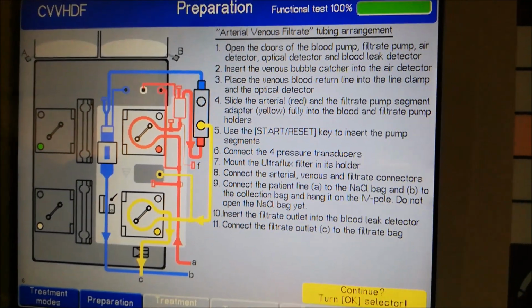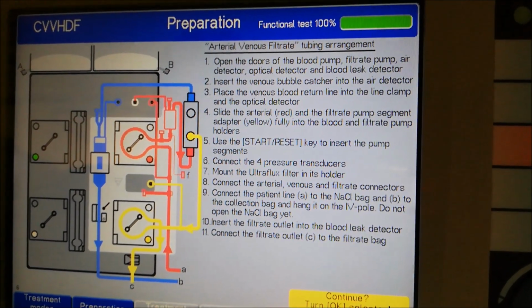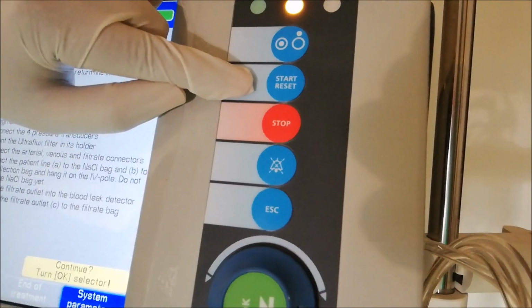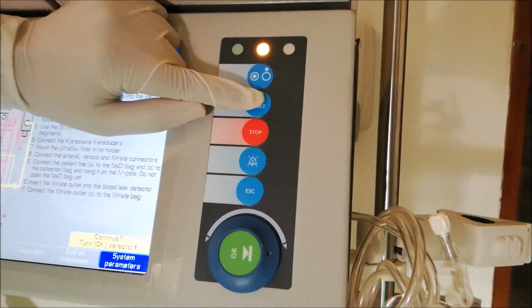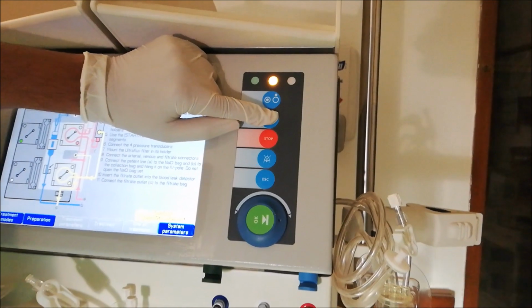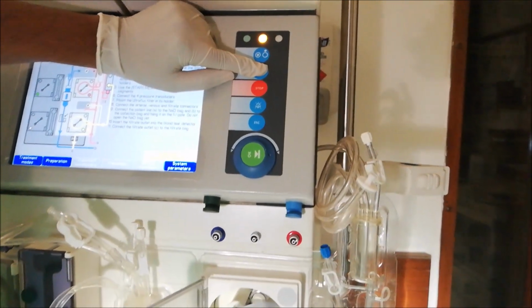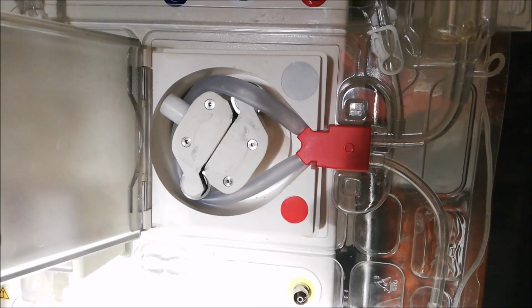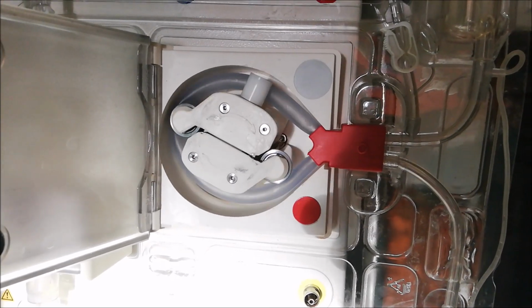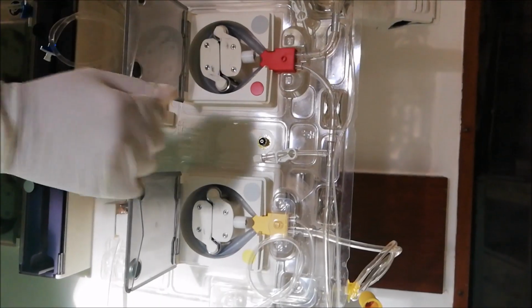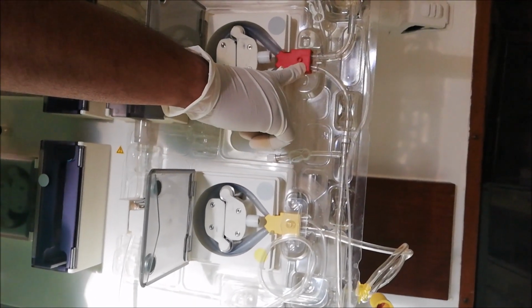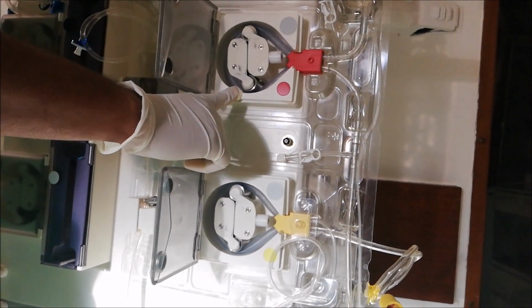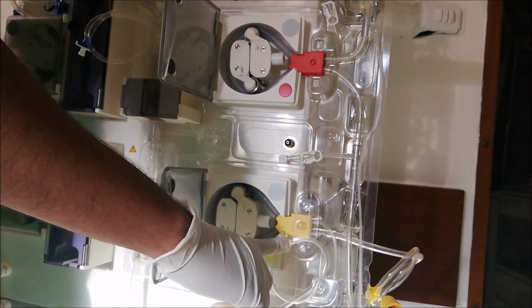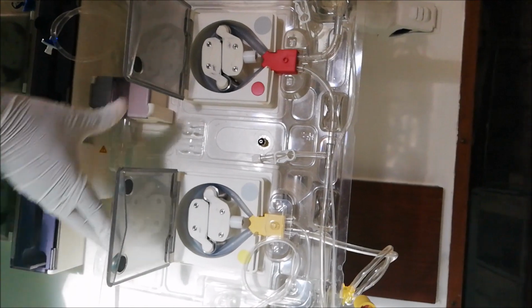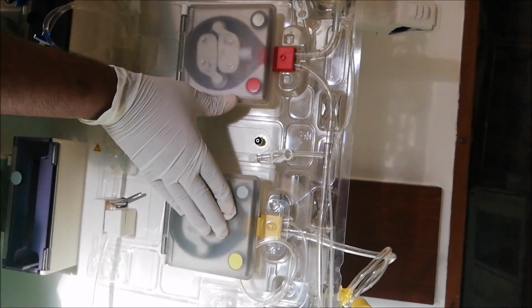Use the start reset key to insert the pump segments. Now I will press start and reset key to adjust the segment into the pump. Now you can see the tubing of blood is fixed into the blood pump and filtrate tubing is fixed into filtrate pump. We will close the door and move on.